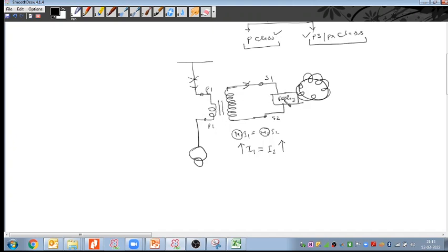And your control panel may be damaged, there might even be a fire in the control room building due to the higher amount of current. So CT saturation is also required in order to protect the relays, the meters, and avoid fires on the secondary side.